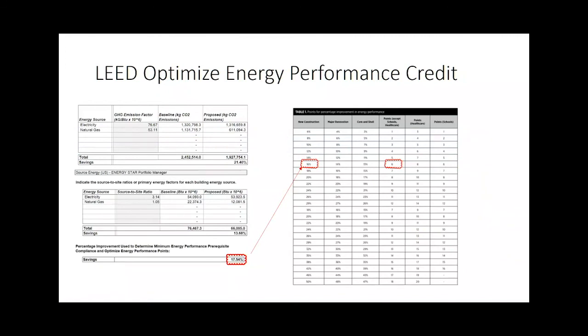The last bit of that calculator averages those two numbers, the two units of savings. When we put those factors into the column for source energy and greenhouse gas emissions, it multiplied the factor by electric use and gas use, giving total greenhouse gas emissions for our baseline and our proposed. We divided those and saw we're saving 21.4% greenhouse gas emissions relative to a code compliant baseline. Source energy did the same process and showed we're saving 13.7% source energy relative to the code compliant baseline, giving an average of 17.5% total savings.